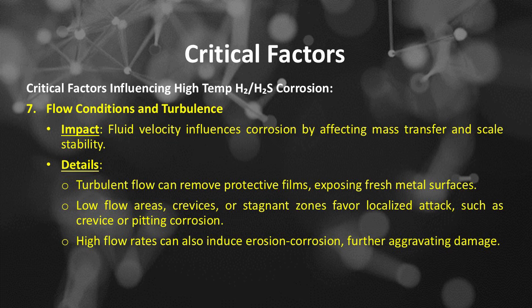Critical factors. Number 7 is flow conditions and turbulence. The flow conditions and turbulence impact. Fluid velocity influences corrosion by affecting mass transfer and scale stability. For details, turbulent flow can remove protective films, exposing fresh metal surfaces. Low flow areas, crevices, or stagnant zones favor localized attack, such as crevice or pitting corrosion. High flow rates can also induce erosion corrosion, further aggravating damage.